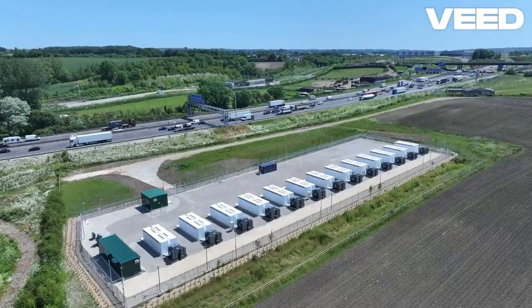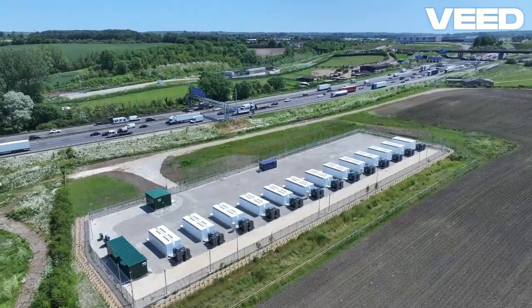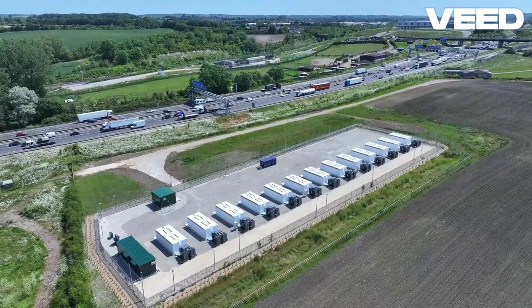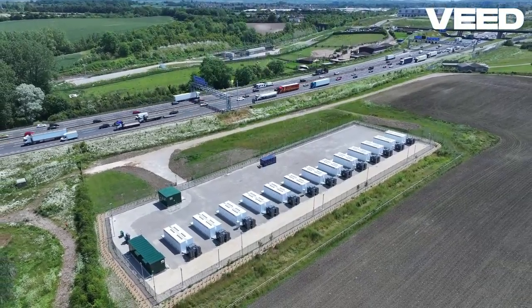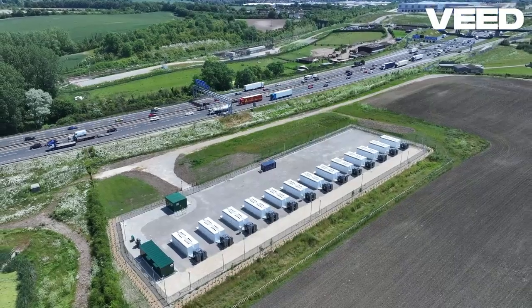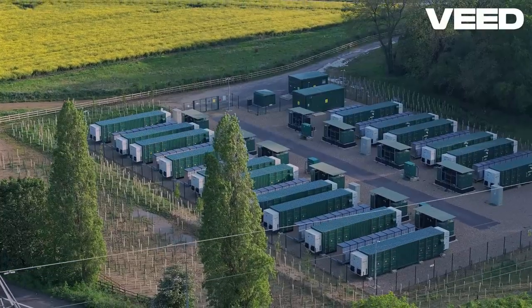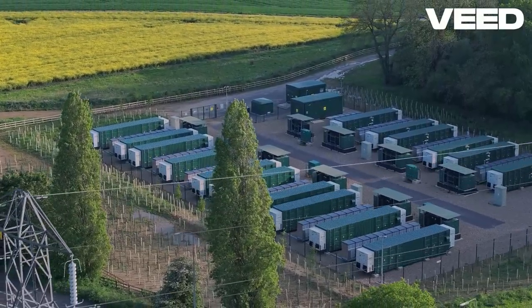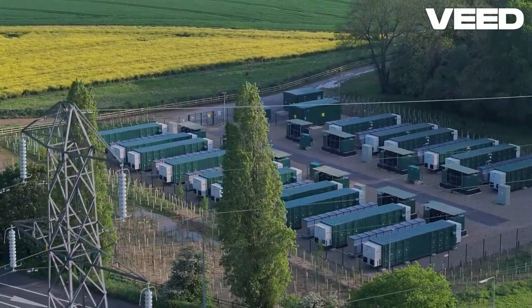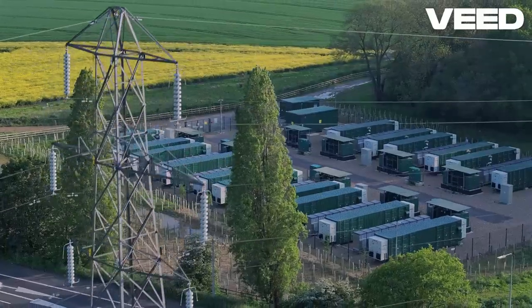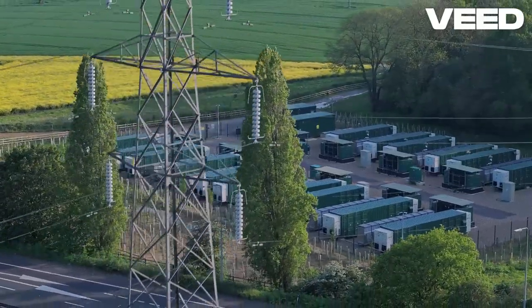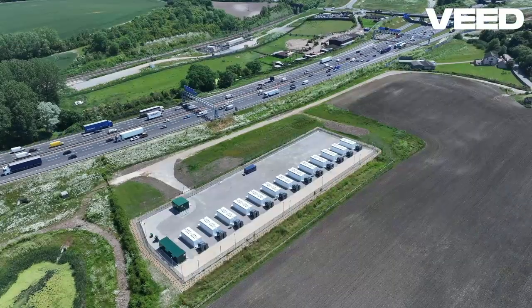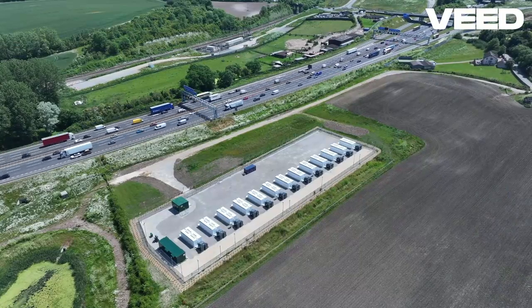Imagine a large industrial region primarily powered by renewable sources. Suddenly, a cloud cover reduces solar generation while a major transmission line trips due to an equipment failure. This double hit causes a rapid drop in frequency. Without sufficient inertia or backup from traditional generators, the grid's frequency plummets from 50 Hz to 48 Hz in seconds.